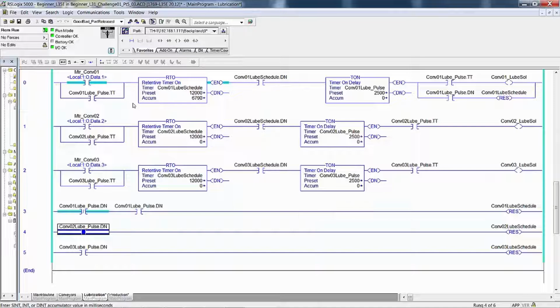Now let's say we turn off motor 1 during this 2.5 seconds. Oh, I was a little slow. See, it kept on going. Now let's do that again. So there's motor 1 running. We've got to get the lube schedule going, and then we're going to turn off this motor by way of the photo eye once we're in this 2.5 seconds. So I turned it off, see, but it keeps going.